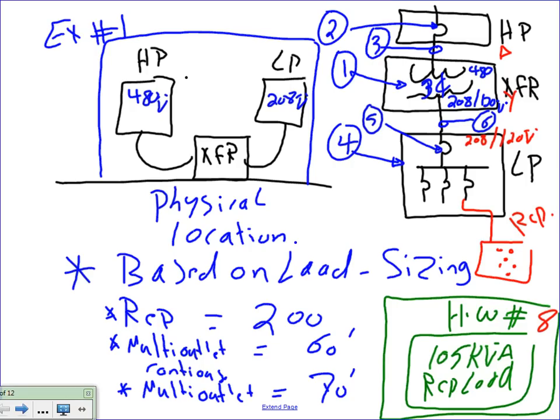How do we size a receptacle transformer? Since it's mostly a receptacle transformer, we size it based on the receptacle load that we have. I assumed that when you did your receptacles in the building, you came up with 200 receptacles, duplex, single or quad. Plus multi-outlet assembly: 60 feet continuous, and 70 feet non-continuous. Do you remember the multi-outlet assembly? It's this right here in front of you.